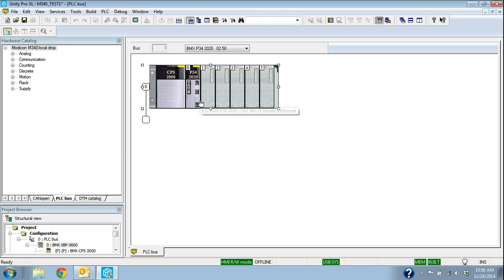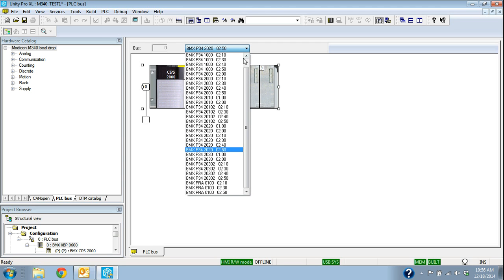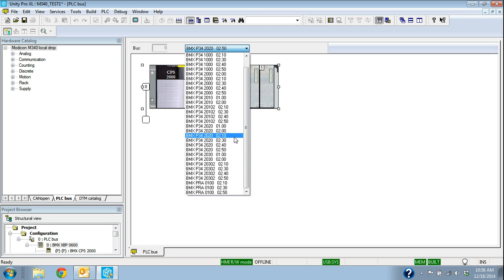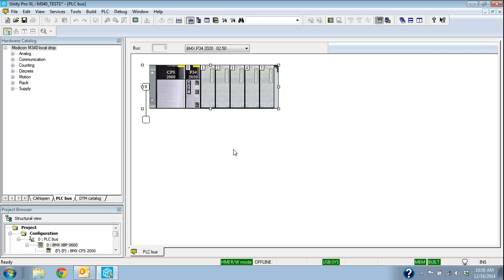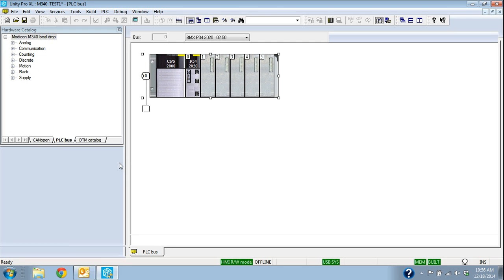Then I could load this on that processor and start programming with it. If it happened to be an older processor, like it was a 2.4 or a 2.3, I can actually change that selection here and back that up to an older firmware if I wanted to. Or I could upgrade the processor with a newer firmware, but those need to match in order for me to load this on a processor.